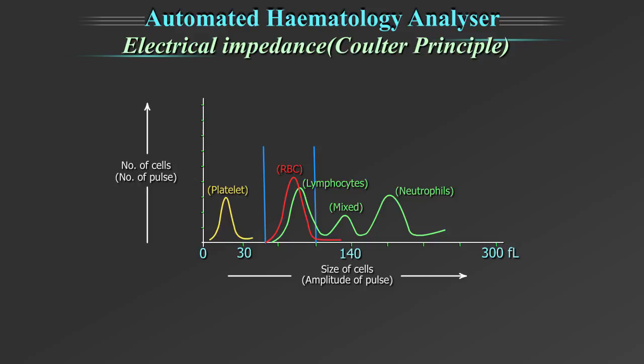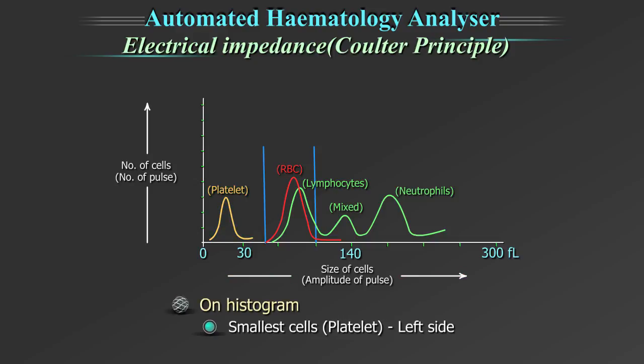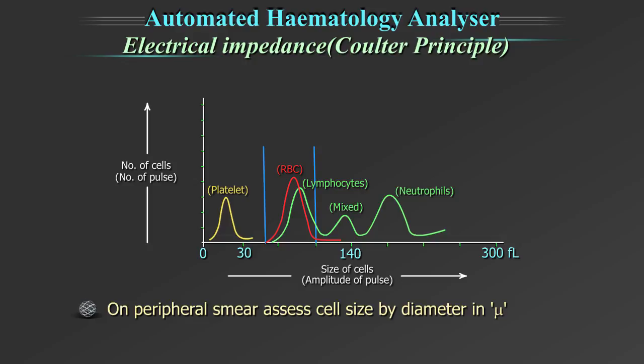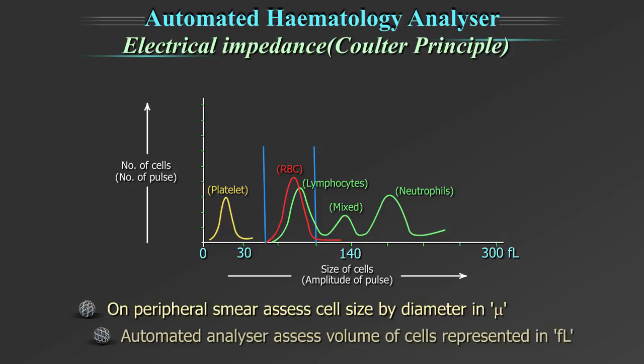Histograms are a graphical representation of numerical data of the different cell populations counted on the cell counter. The x-axis represents the size of the cells in femtoliters, assessed by the amplitude of the pulse. The smallest cells, that is the platelets, are represented on the left side of the histogram, and the largest cell population is represented towards the right side. On a peripheral smear we assess cell size by its diameter in micrometers, whereas in an automated analyzer we assess the cell volume, which is represented in femtoliters.